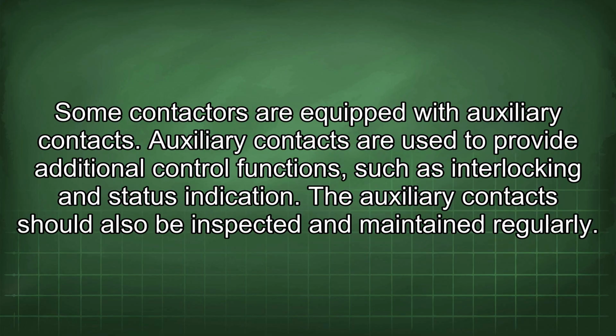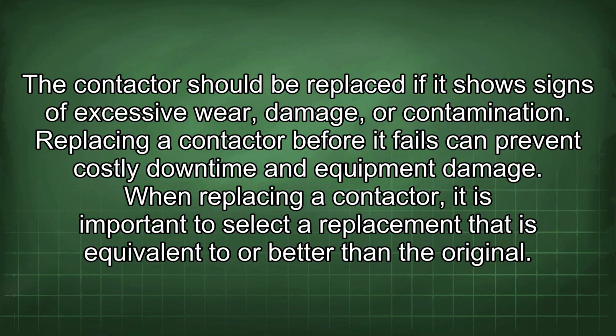Some contactors are equipped with auxiliary contacts. Auxiliary contacts are used to provide additional control functions such as interlocking and status indication. The auxiliary contact should also be inspected and maintained regularly. The contactor should be replaced if it shows signs of excessive wear, damage, or contamination. Replacing a contactor before it fails can prevent costly downtime and equipment damage.